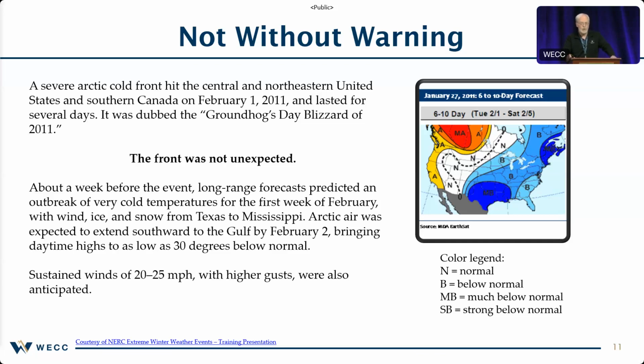And the reason they do all this forecasting is that when the cold weather arrives, when they hit the real-time operating window, they want to balance the amount of generation they have to the amount of load that they're going to serve, with a little extra reserve in case you lose a generation here or there. So that during that real-time window, the system operators, the RCs, the balancing authorities, the TOPs, can operate the system in a reliable manner. And what we're going to see in the events we look at is that the balance between generation and load is skewed. Sometimes it's a miscalculation on forecasts that they did. Sometimes it's just loss of generation.